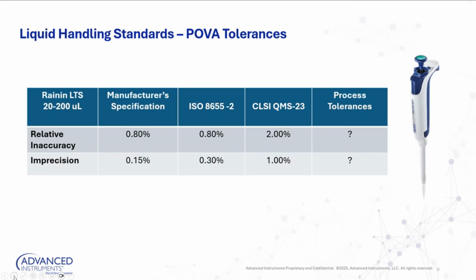And then we've got the CLSI standard. They indicate relative inaccuracy of plus or minus 2% and imprecision of 1%. So then where does that leave you in the decision making? Because all of the standards indicate that you could also implement your own process tolerances when it comes to what's considered passing or failing for this one pipette.